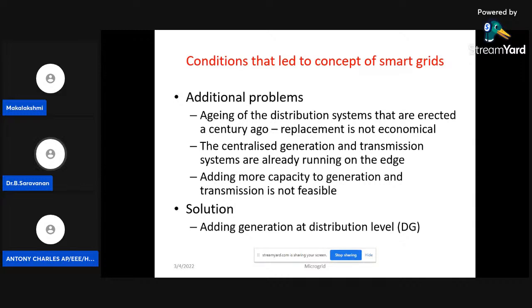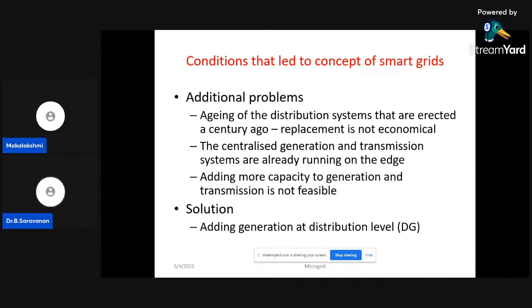The costliest thing in the entire power system is the power transformer. Once the power transformer fails, we don't have any backup standby transformer because of its cost. Suppose you have a motor in your house - if something goes wrong, we can go for a standby motor because it's feasible and affordable. But in a generating station, the complete generation, maybe 7 units of 220 megawatt each, is fed back to one or two transformers. We don't want to keep a transformer standby. That's why adding more capacity to generation and transmission is not feasible.